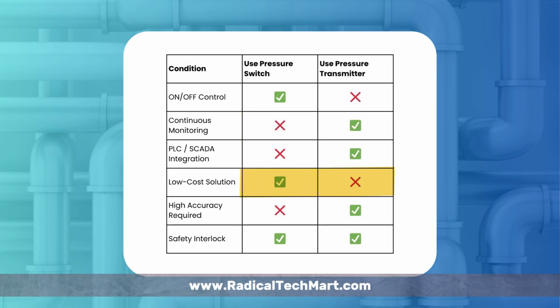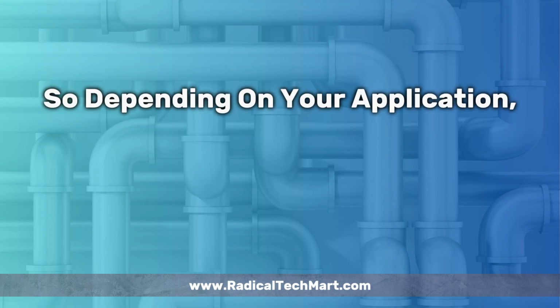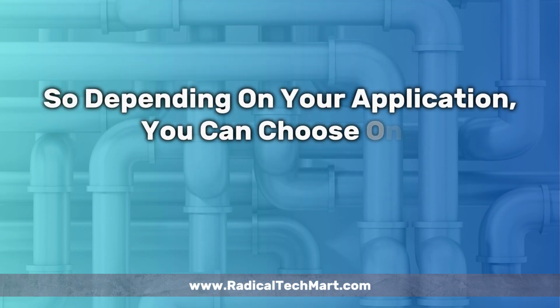When you're looking for a low-cost, easy-to-maintain solution, choose a pressure switch. However, if high accuracy and data precision matter more, go for a pressure transmitter. And for safety interlocks or critical applications, the best practice is to use both together, the switch for control and the transmitter for monitoring.